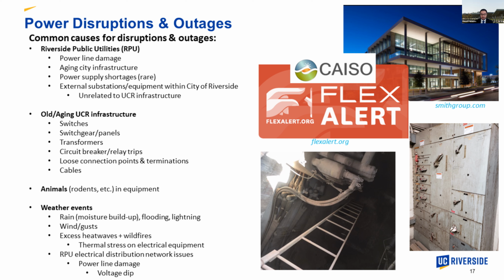Weather events are a really big one, like I just mentioned—everything from rain, flooding, and lightning strikes. The thing about rain is it's tricky, because if you build enough moisture within a certain piece of equipment, that could create a path for electrical current to flow through. Same thing with winds and gusts—if enough dust builds up on insulators or circuit breakers within the substation, that could cause a pathway for current to flow and cause a catastrophic system fault. So whenever extreme weather events happen, our facilities group is out there making sure everything is okay with the resources we have.